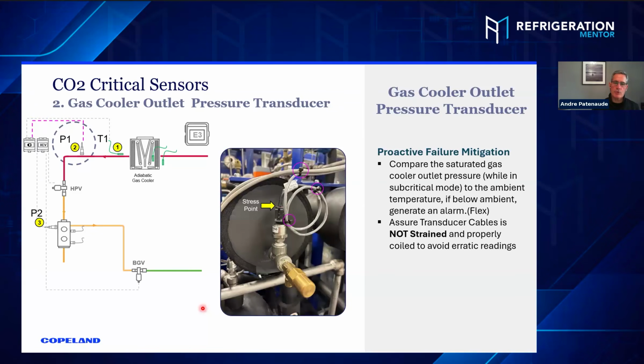But one of the things that Brent Cheshire told me, he said, man, a big problem with pressure transducers is this stress point right here. That wire gets pulled at a 90 degrees. It gets tugged, and all of a sudden you get a short in that transducer. Be careful to stress relieve that point. Little tie wraps, make sure it doesn't get stressed as it's pulled. Yeah, big problem in the field. Just a little cable. So keep that in mind, because there's a lot of pressure transducers out there.